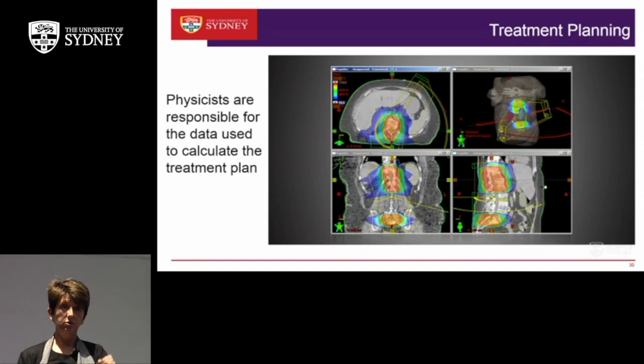And we put in measuring devices. This is an ion chamber. This is made of carbon, and inside the carbon is an air cavity. So the radiation comes in, it ionises the air in the cavity. There's a central aluminium electrode, and that measures the charge that is generated in the air cavity, and from that we can work out what dose of radiation is being delivered at the point where the chamber is being held.